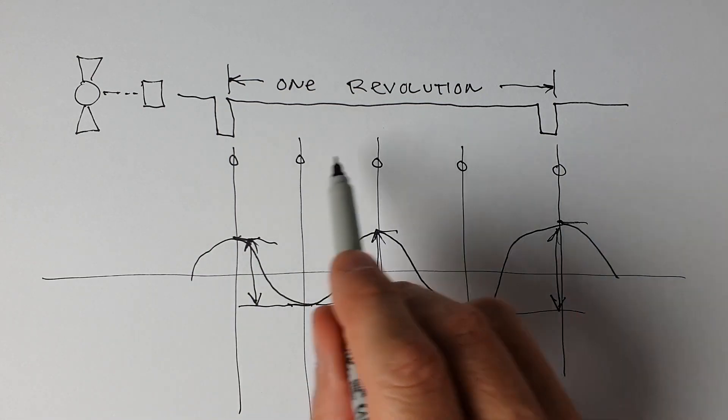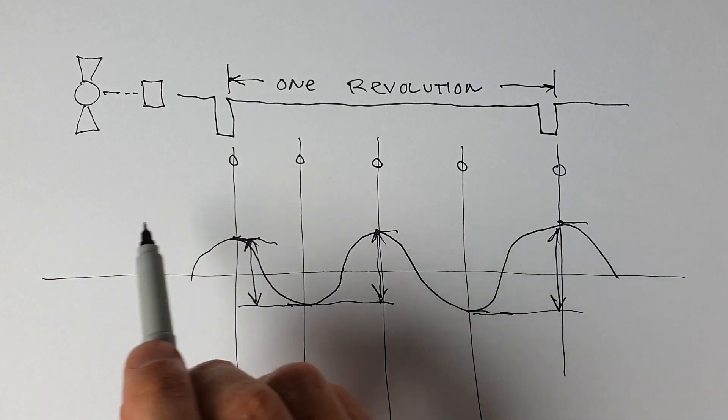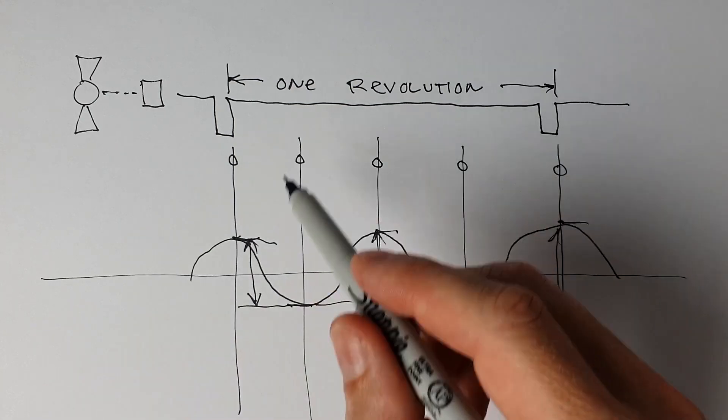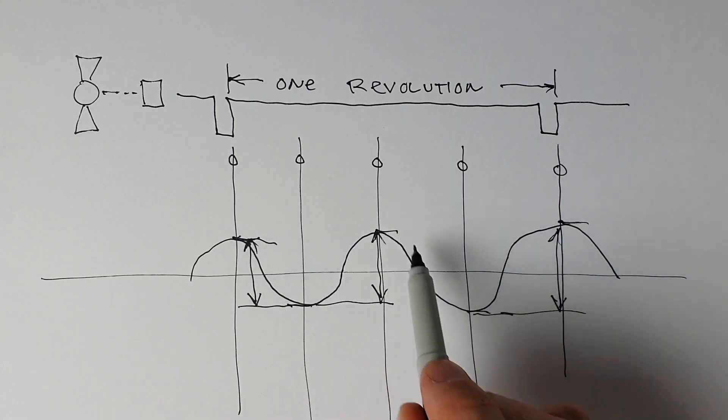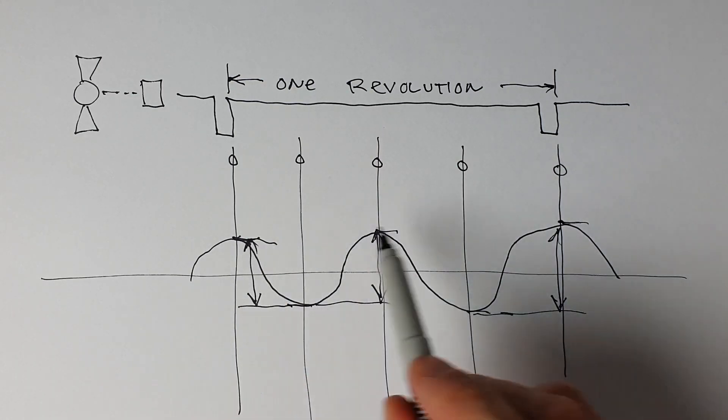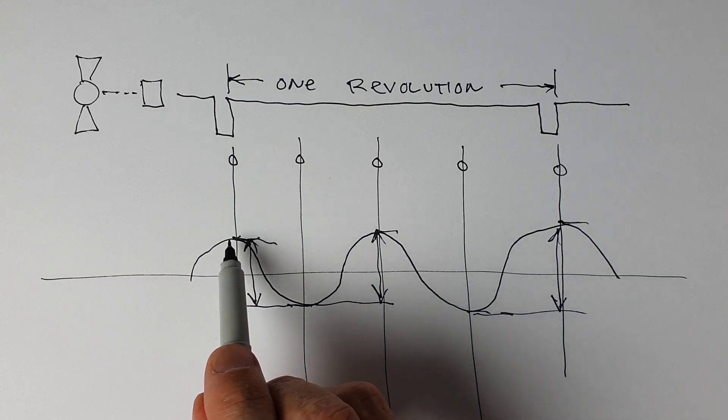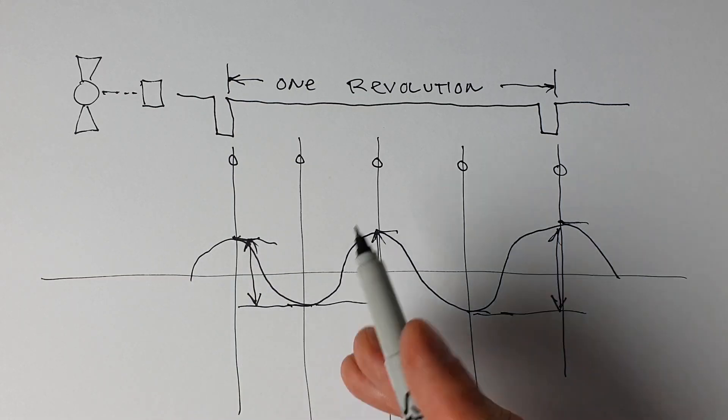And we're doing that synchronous with the revolution of the shutter and that gives us the ability to reject any noise that's not exactly synchronous with this process. So this is what you call synchronous demodulation. So we're taking an A to D reading at each one of these points.